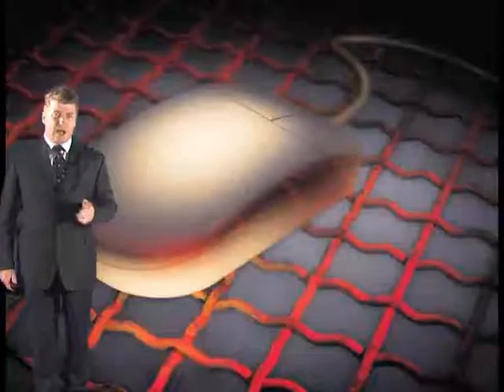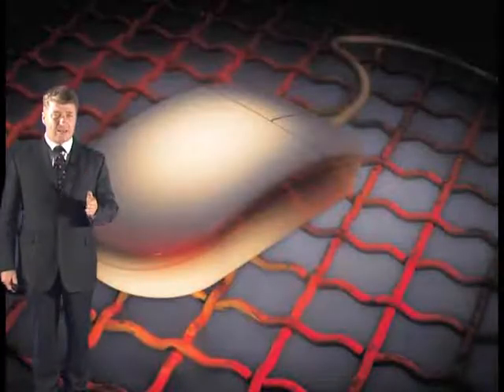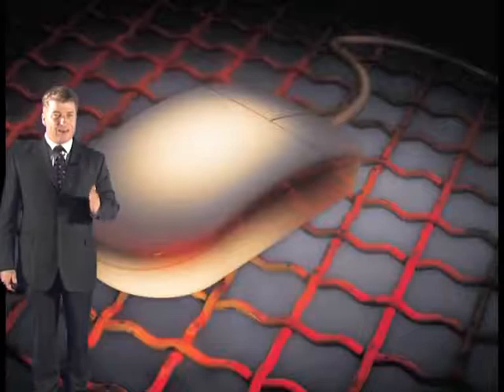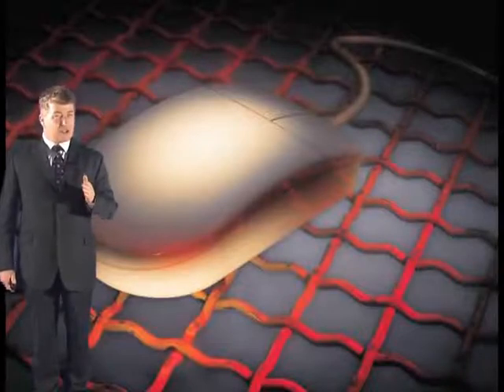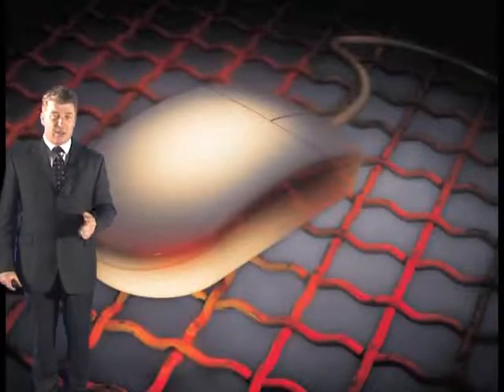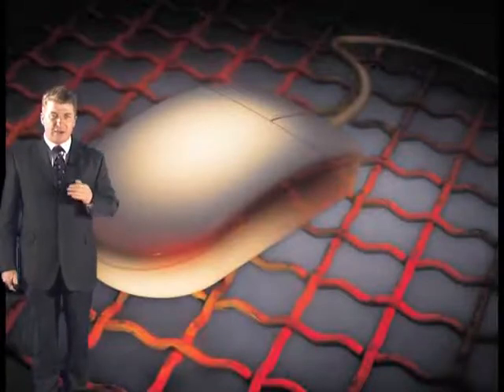Now, it is surprisingly common that new proposals from fire engineering companies often show a lack of understanding of smoke control, and they often place heavy reliance on computational fluid dynamics analysis, which is often based on assumptions that are neither realistic nor rigorous.